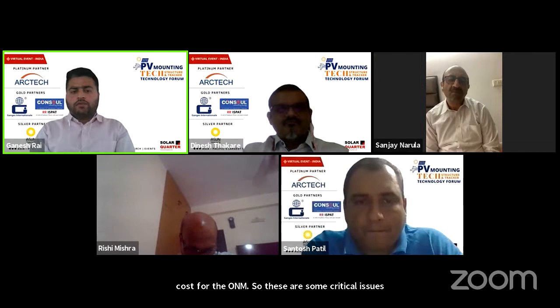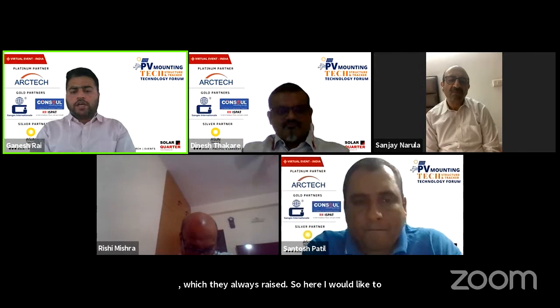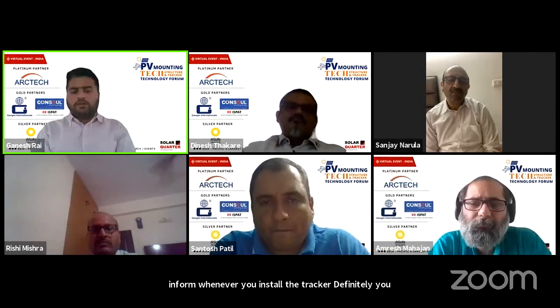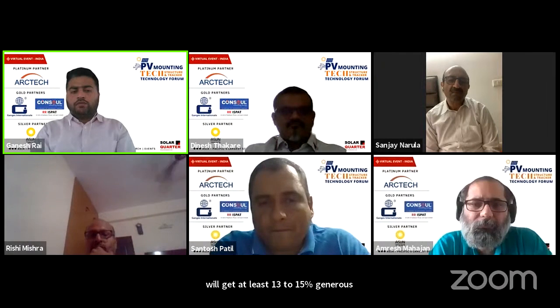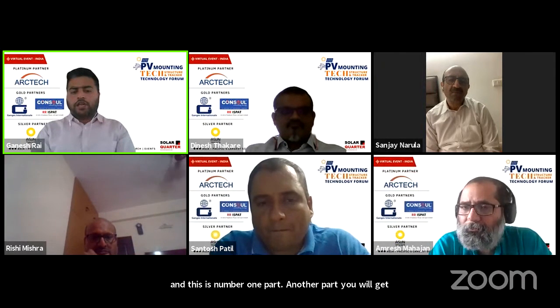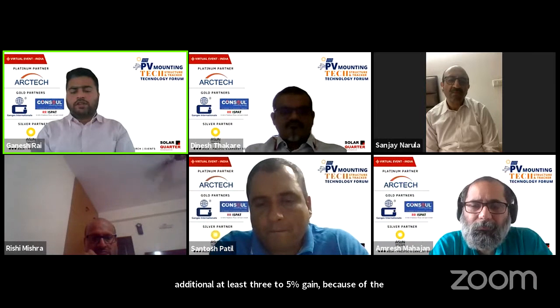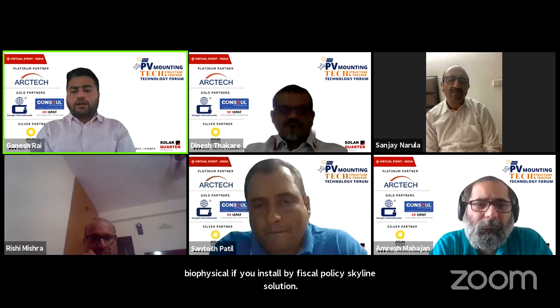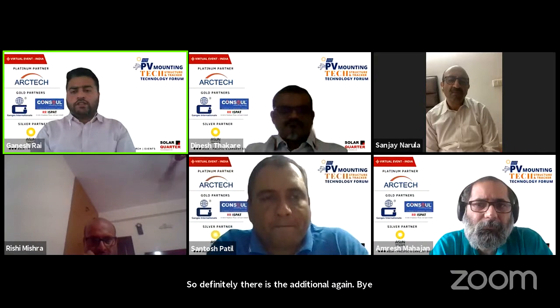So here I would like to inform, whenever you install the tracker, definitely you will get at least 13 to 15% generation. This is number one part. Another part, you will get additional at least 3 to 5% gain because of the bifacial, if you install bifacial plus Skyline solution. So definitely there is additional gain, but on the other side, definitely you need to pay some cost.